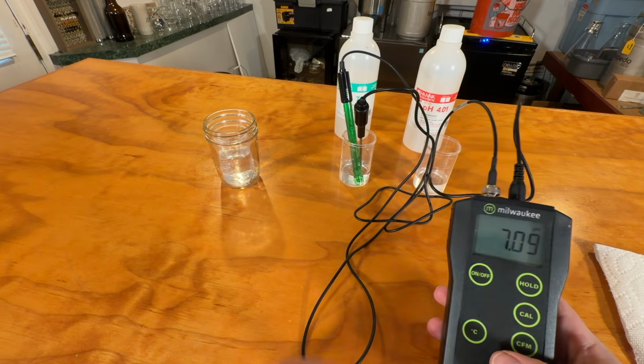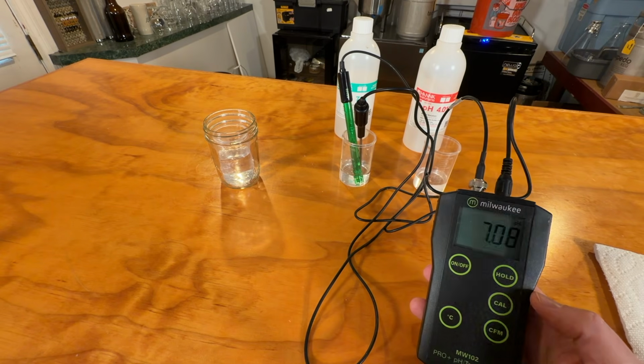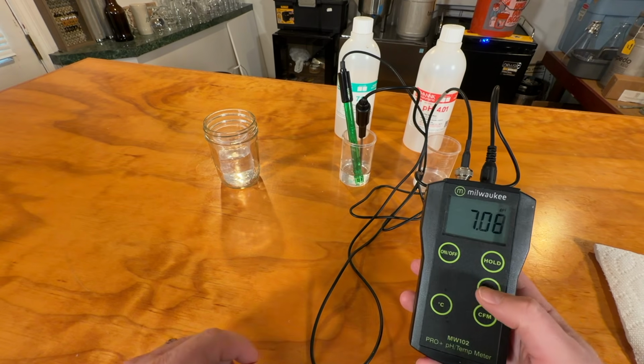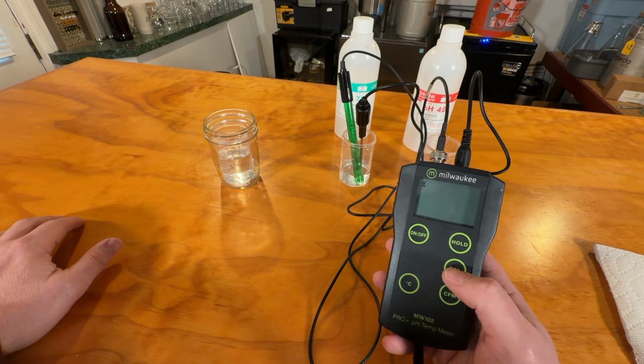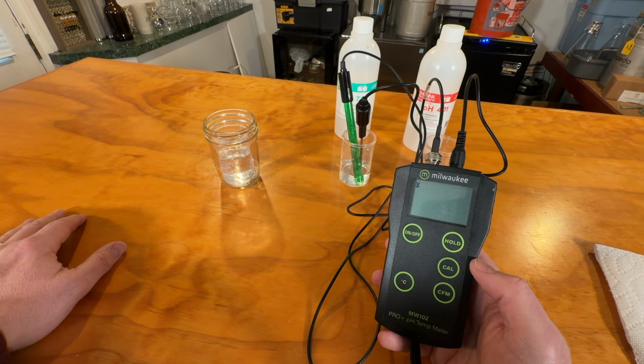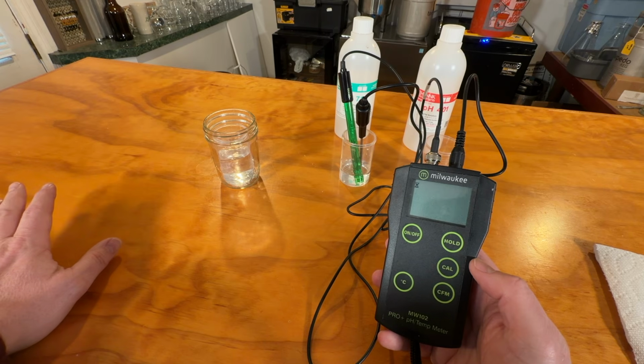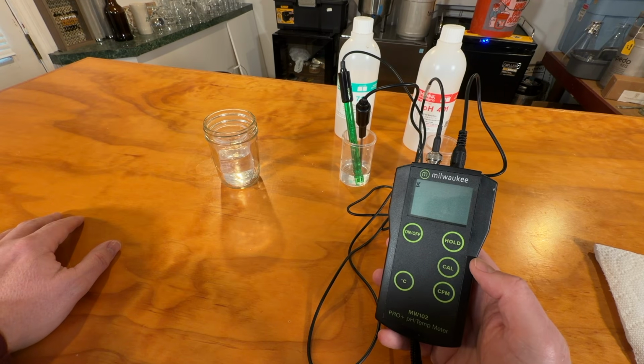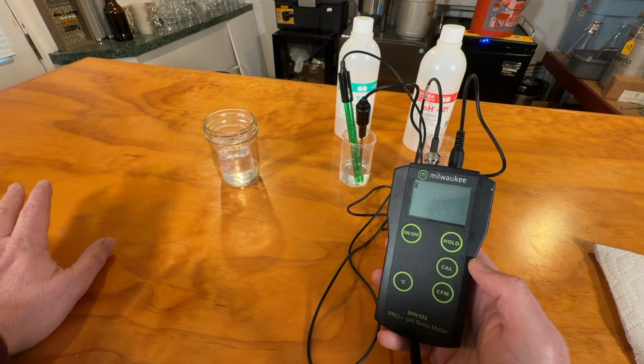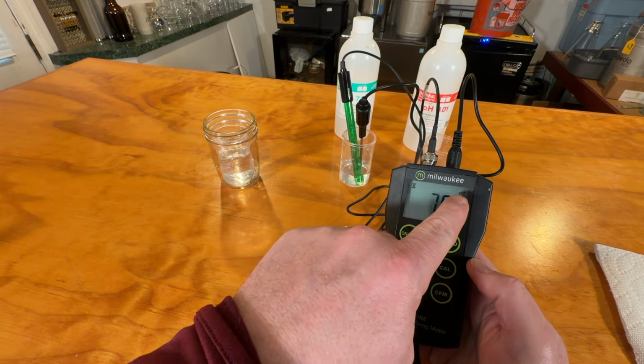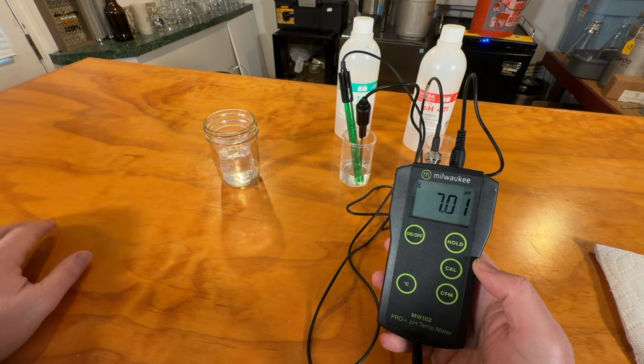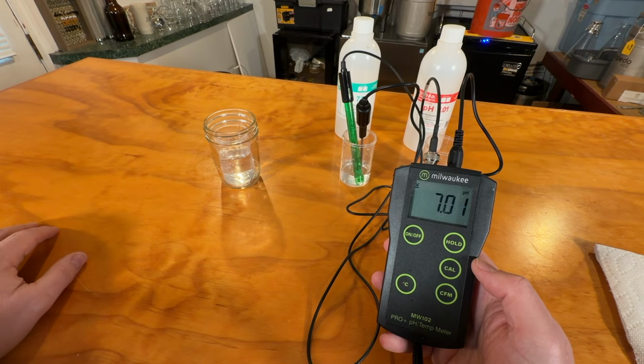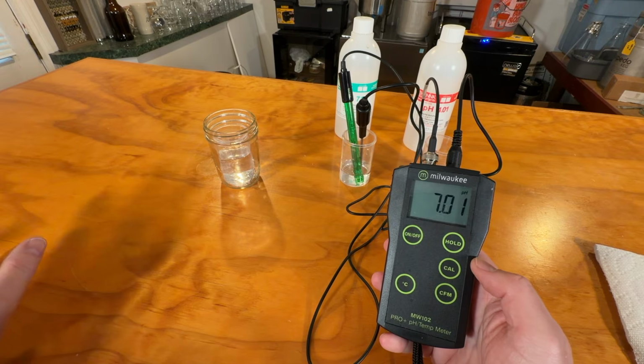So we're in there, and right now it's reading 7.09, so that's pretty close. But what we do is we just hit calibrate, and it's going to start flashing 7.01. And it's going to do that until it feels like it's got a stable reading, and at that point, the 7.01 won't stop flashing, but the little pH up in the corner will go solid. The hourglass will stay on this meter. Oh, actually that went away. In the past, that hasn't happened. Okay, cool. So there you go.